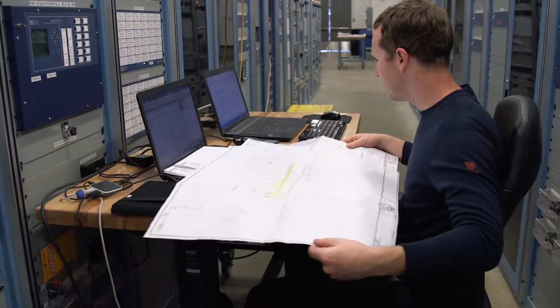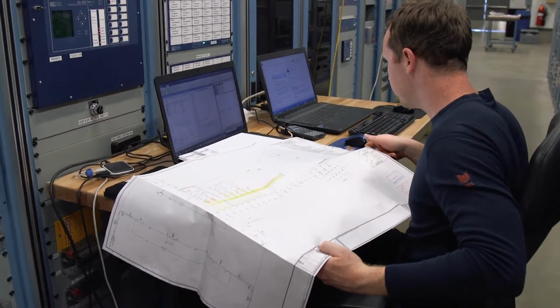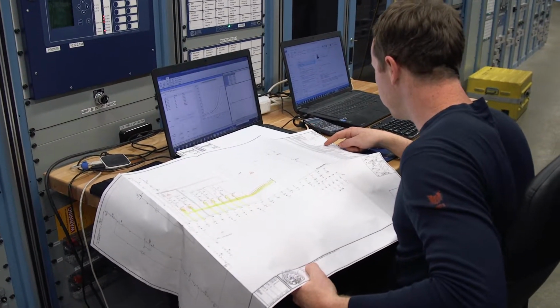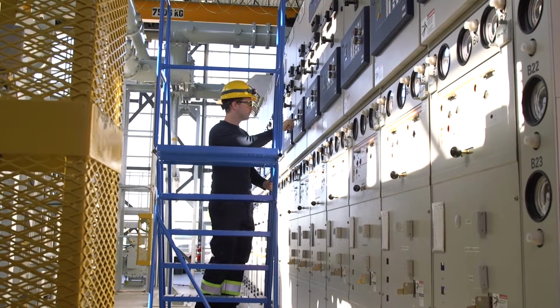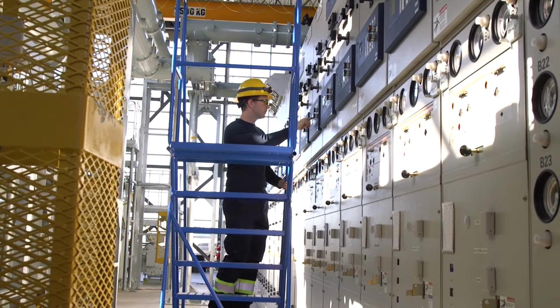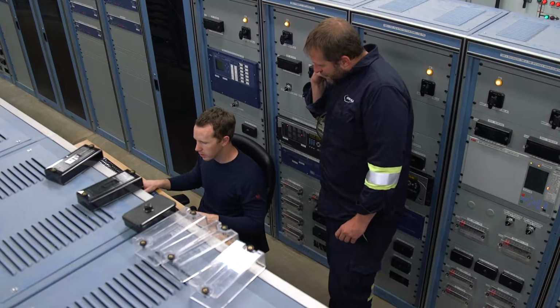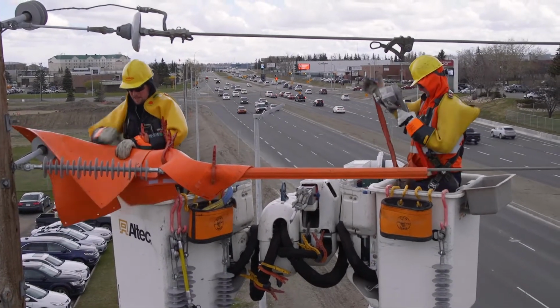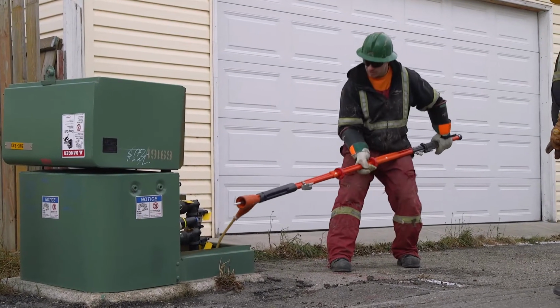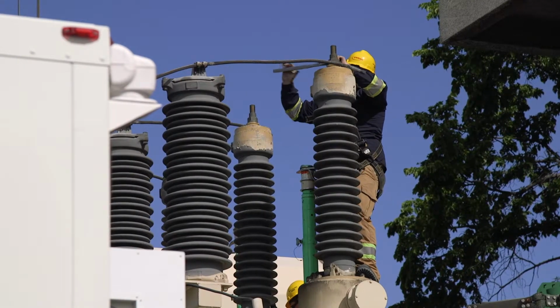So we're ensuring that the relays are properly calibrated, programmed, and set up to issue the tripping signals to the proper parts of the system, to isolate the problem and the fault as much as possible, and localize it so that not too many customers are taken out of power. The other groups then kick into gear as far as actually fixing the problem, and then we can put it back into service.